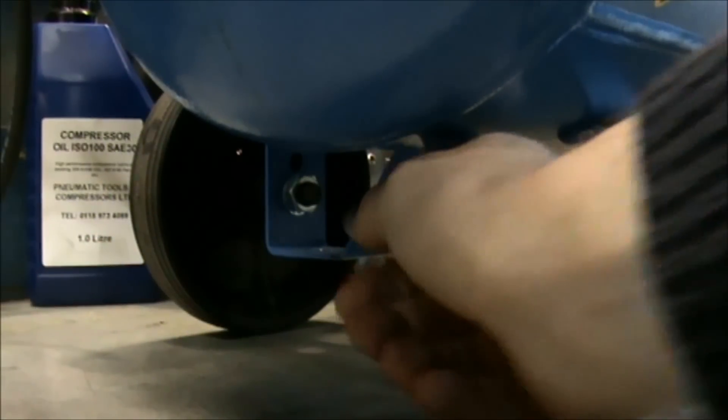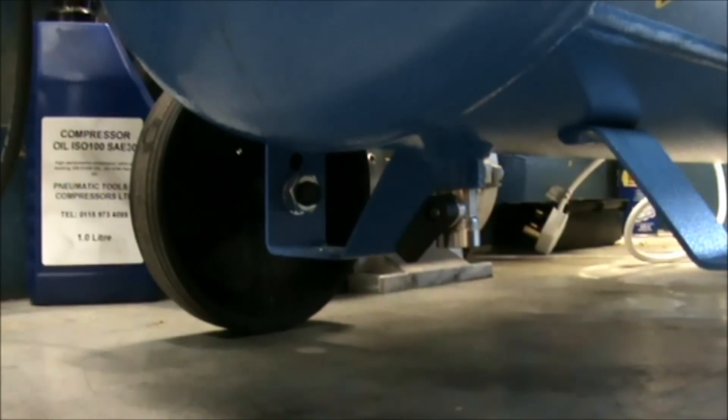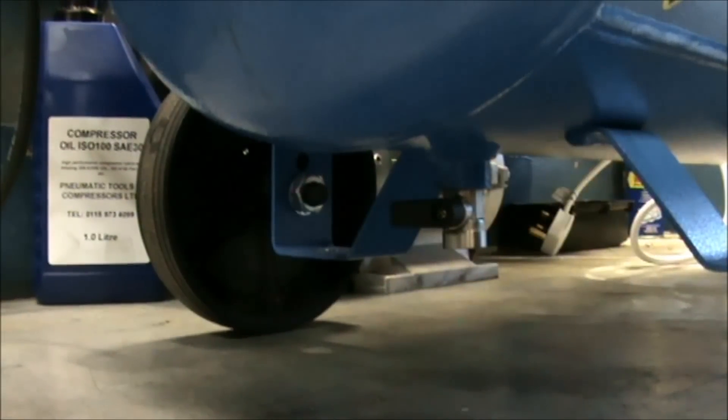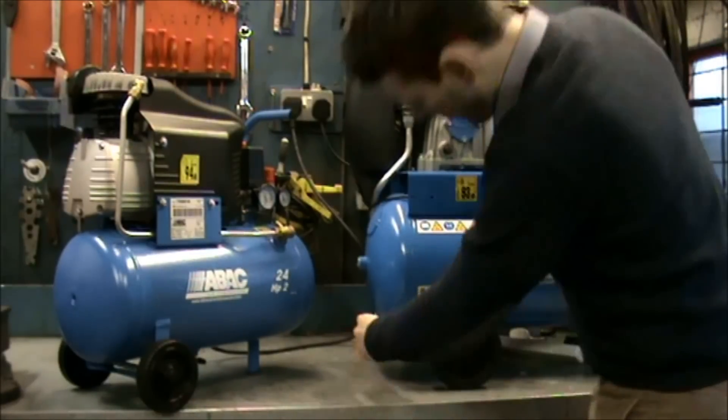Condensate water is caused by compression and temperature in the system. You need to remove this water because it can be carried over into your airline and corrode your air receiver, causing long-term damage. We would recommend draining the tank every day, at a minimum once a week.